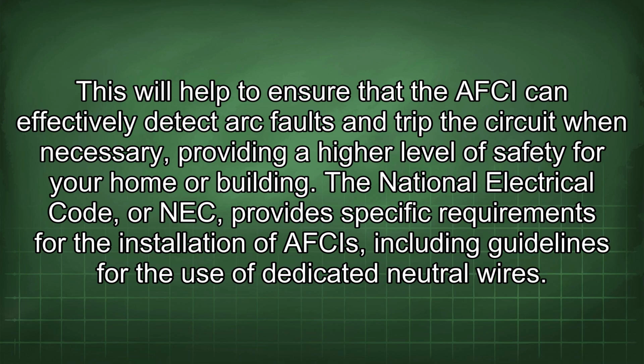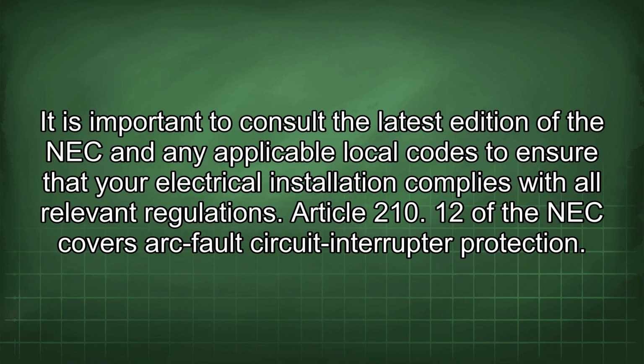The National Electrical Code, (NEC), provides specific requirements for the installation of AFCIs, including guidelines for the use of dedicated neutral wires. It is important to consult the latest edition of the NEC and any applicable local codes to ensure that your electrical installation complies with all relevant regulations. Article 210.12 of the NEC covers arc fault circuit interrupter protection.